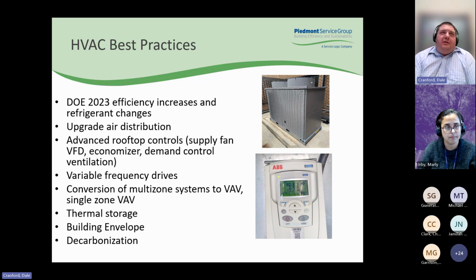I would recommend, if you're looking to implement variable frequency drives, that you make sure that your systems are able to do that. So for instance, on the fan side, you either need to have VAV boxes that are putting static pressure feedback to the control system so that you can actually back down the speed of those fans. Or we have a lot of applications for single zone VAV where we can modulate fan speed up and down based on the relationship of space temperature to set point. On the pumping side, making sure you have two-way valves throughout most of your system. You do need at least one three-way valve to make sure you get flow back to your central plant. And then we talked about conversion of multi-zone systems to VAV and the single zone VAV applications.